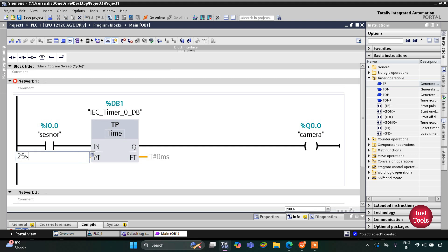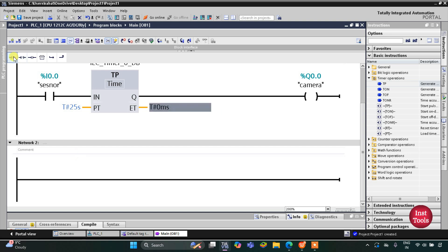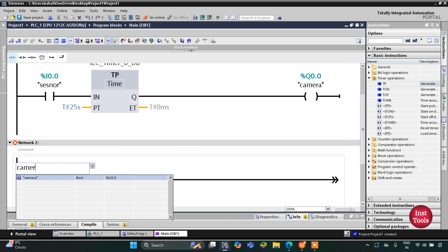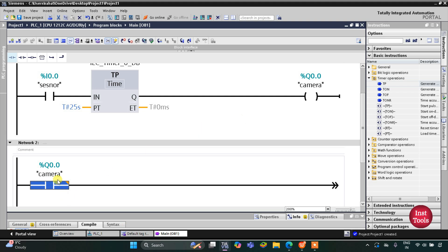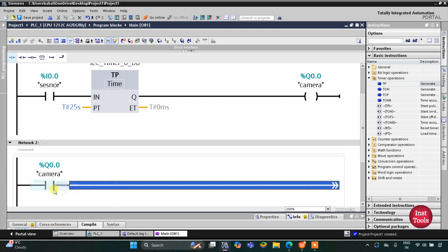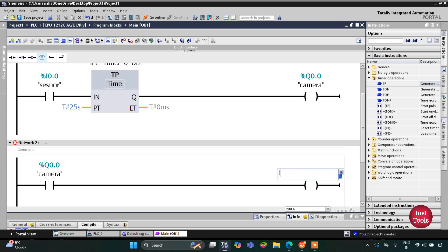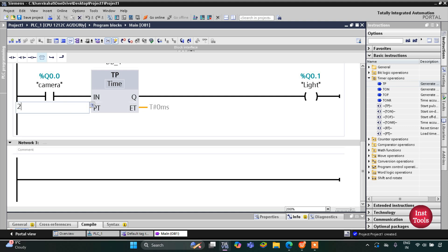In Network 2, I will insert a normally open contact and use it as the camera input. When the camera turns on for 25 seconds, current flows through this contact for 25 seconds. During that interval when the camera is on, the light will also turn on. However, the light remains on for only 2 seconds, so we will use another TP timer with a preset value of 2 seconds.